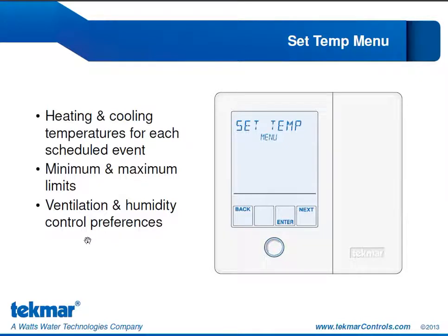The set temp menu is also where we're going to program our ventilation and humidity control preferences. So here is where we set up our relative humidity minimum and maximum percentages for the occupied and unoccupied times. Also where we're going to configure our ventilation. So we turn our ventilation mode on or off in the setup menu, and we configure it in the set temp menu. So this is where we set it to auto, a percent on time, or on.